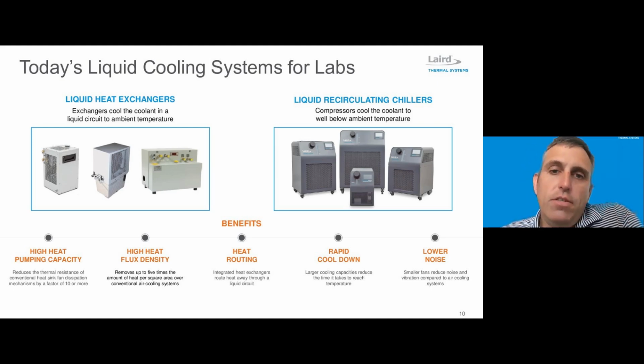Heat routing is very simple with liquid cooling systems. We can put fluid through a 1/2 inch or a 12 millimeter hose that can go to and from the application and remove kilowatts worth of heat. And when you think of that in comparison to an air duct, it would be many times that, and you'd also have all this air that's kind of howling through the duct. So it's very simple to get the heat from the application out into, say, an equipment room where the cooling system could be installed. These systems, because they have higher cooling capacities, also have the ability to cool down rapidly. So a 5 kilowatt system that maybe is on startup that needs to get to temperature, get to the set point, can do it in a matter of minutes, given the flow rate that's running through the system.